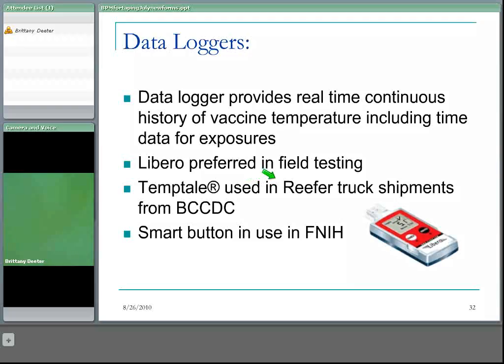Temptale comes with a prepackaged envelope for shipping it back, and is accurate to 0.2 degrees. The Smart Button, purchased by First Nations and Inuit Health, is accurate to 0.5 degree but requires additional hardware purchases — like a small stand — to read the data in the field.